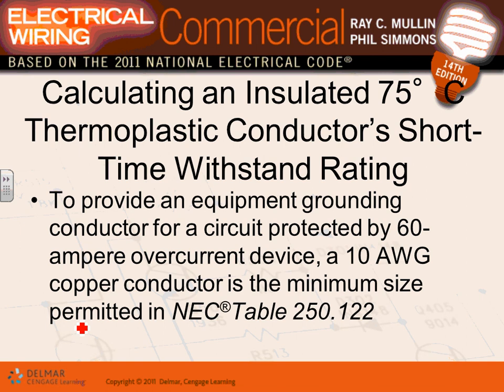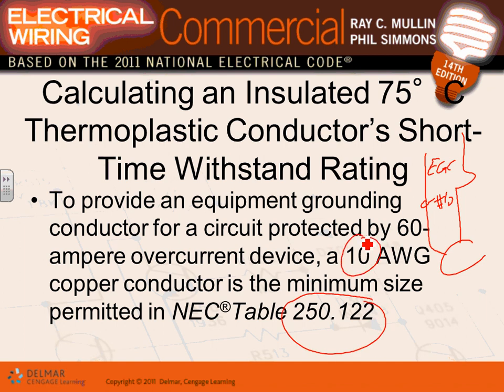Here's a good example, guys. If you have an equipment grounded conductor, this is just for a ground fault. If you have a piece of equipment here and you need an equipment grounded conductor, this is my equipment grounded conductor. This is a number 10 wire, sized based on this table, based on, I believe, a 60 amp circuit breaker. Okay. So depending upon what type of fuse you put on this conductor, you can cook that conductor.